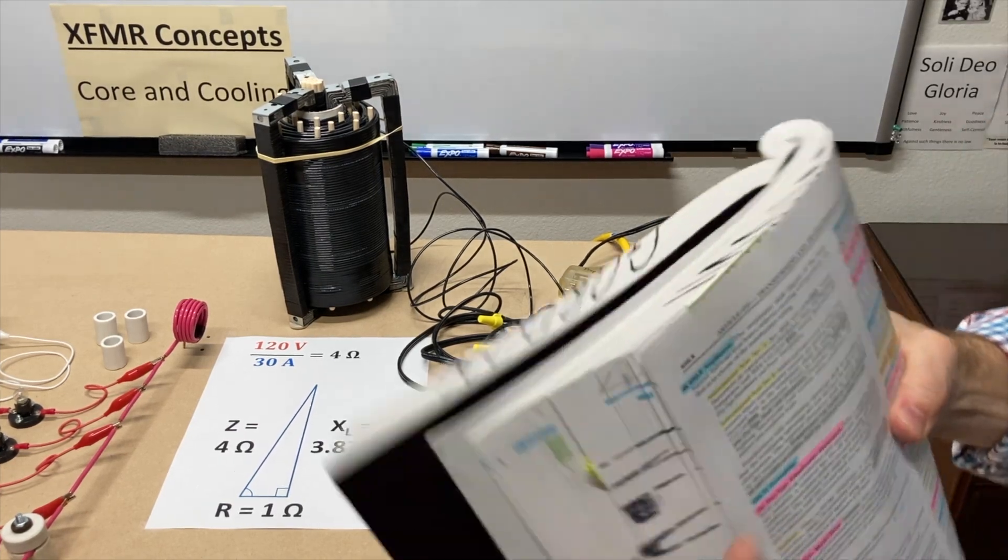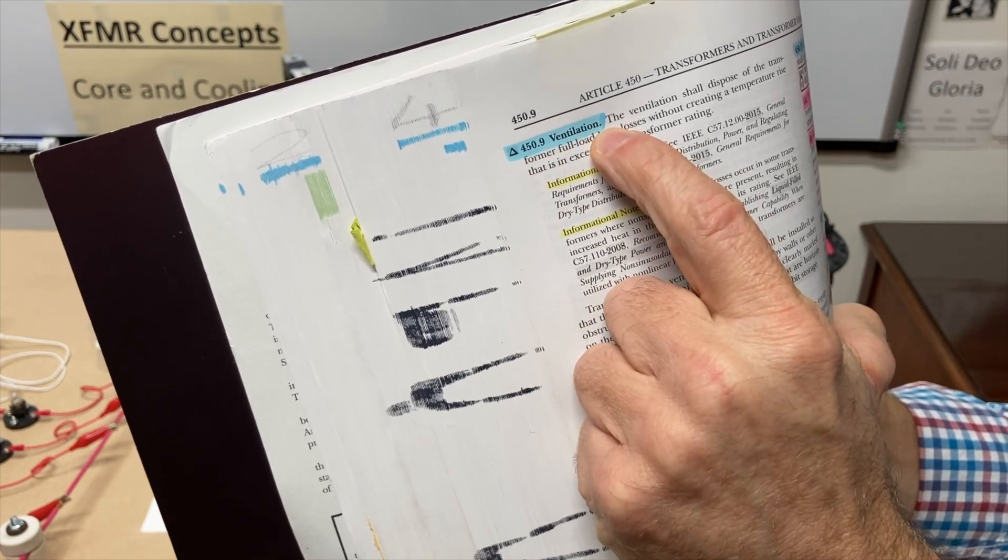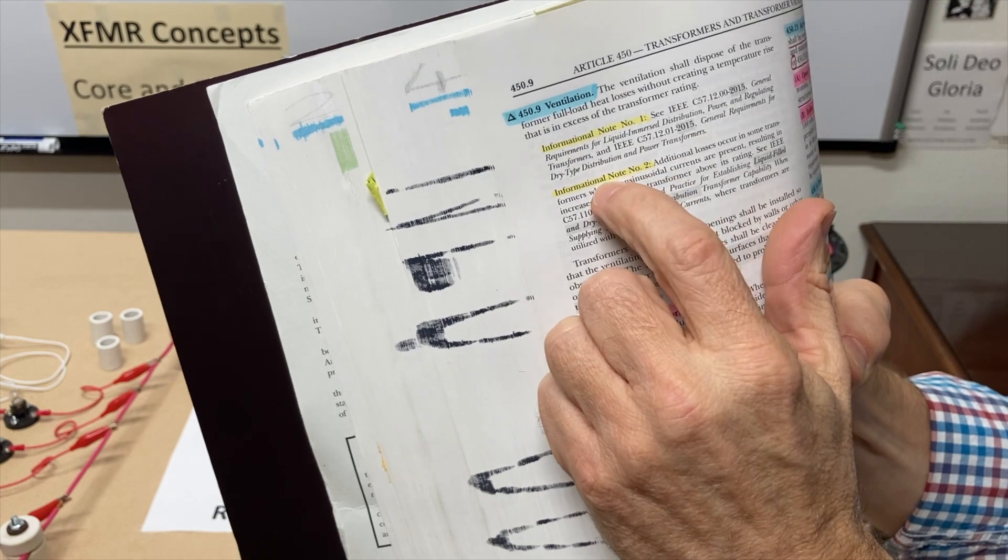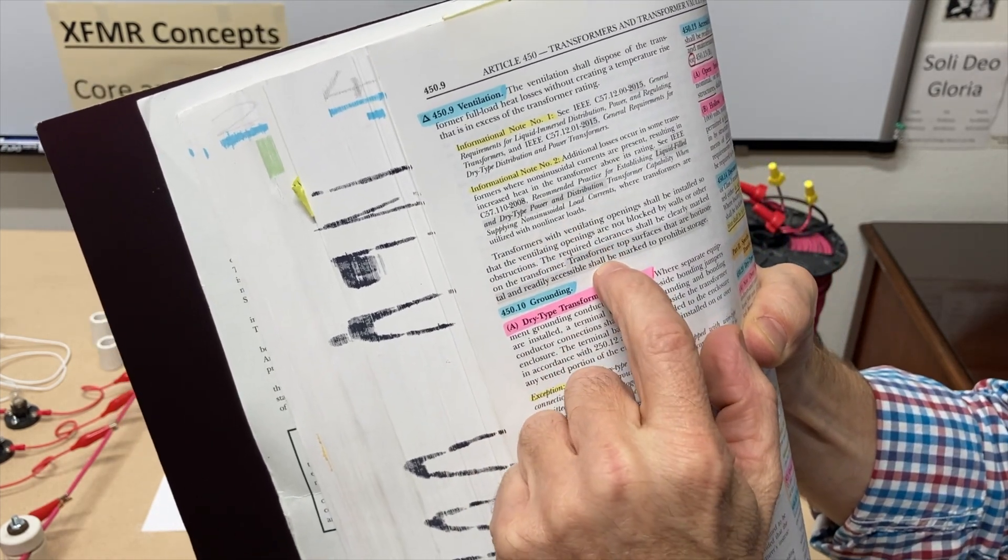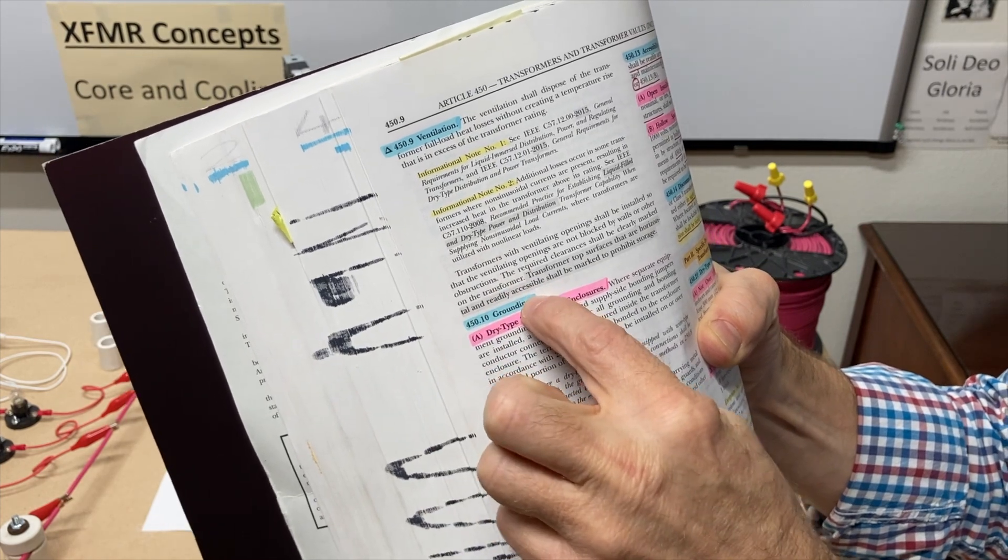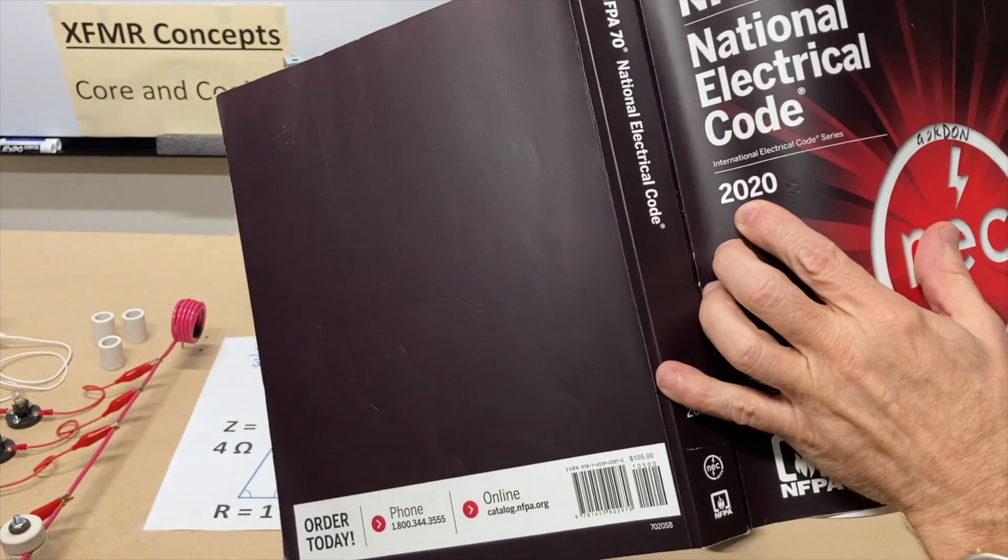So I want to show you something about cooling in the code or rather ventilation. A couple of points I want to make here just quickly on 450.9 on ventilation. Now, there's one sentence here. I'll let you read it later on your own. But is that all there is to this section? Because it jumps to the informational notes. Well, one of the lessons here is you're never done with a code section until you get to the next one. Because there's three more important sentences down below. These info notes apply up here. Or if you have exceptions, always read through till you get to the next section.